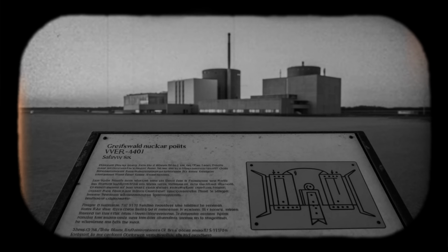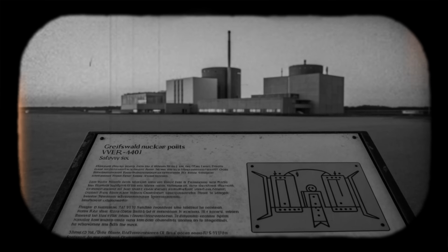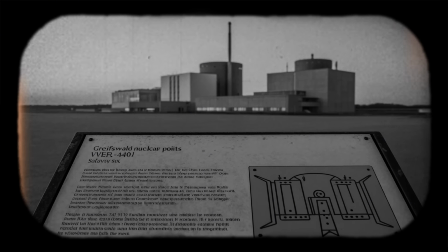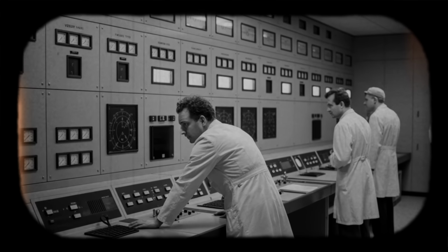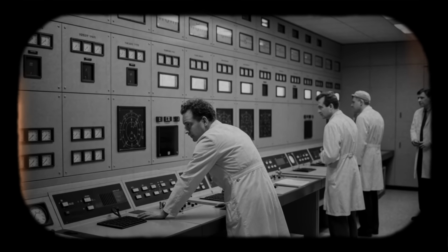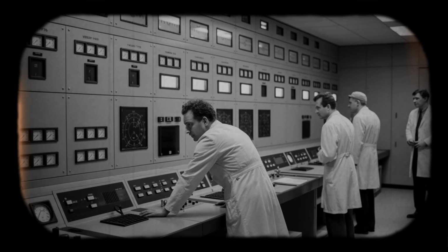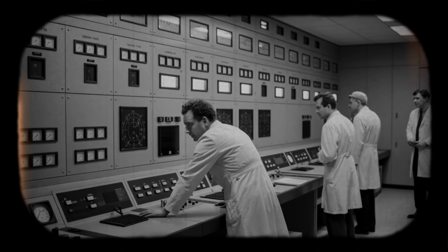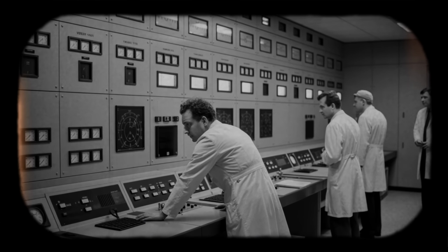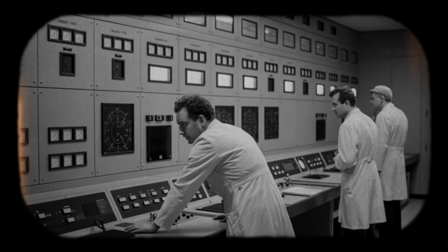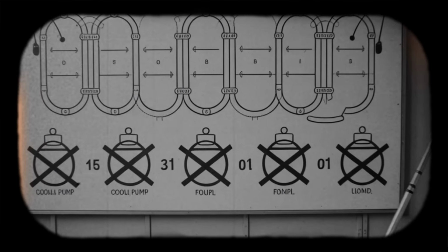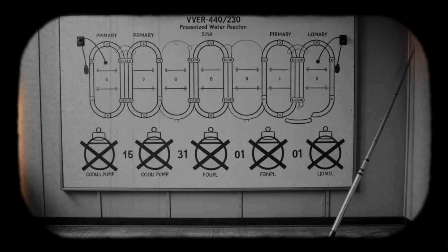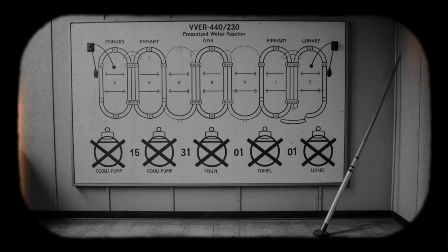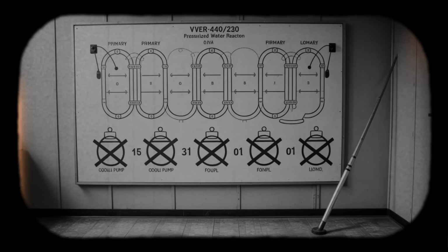Greifswald shifted thinking from local cabinet fire scenarios toward plant-level common cause events in probabilistic models. It showed that cable routing, a detail often treated as a construction and installation issue rather than a safety-significant design choice, could determine whether a plant survived an internal fire without core damage. Soviet-designed plants had a reputation for strong adherence to detailed operating instructions. Procedures were comprehensive, prescriptive, and expected to be followed. Accident management concepts as understood in Western practice, flexible, symptom-based approaches that gave operators latitude for creative responses, had not yet fully developed in VVER operating culture of the mid-1970s.